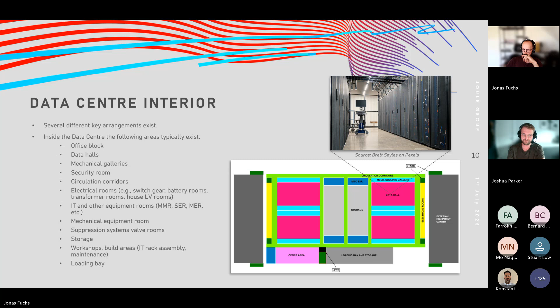So how does current regulation and guidance see data centers? The answer is it doesn't really see it at all. Typically under the building regulations, a data center falls under a Class B building for general industrial use and storage and distribution, often leaning more towards the storage and distribution side. That leaves quite an open gap in how you apply guidance and what are the applicable pieces of guidance to achieve compliance. Ultimately, we don't design data centers as storage facilities. They are quite a bit more than that, given typically the property protection requirements. That isn't picked up within the building regulations, but there isn't any specific allocation towards data centers within the building regulations or supporting frameworks.